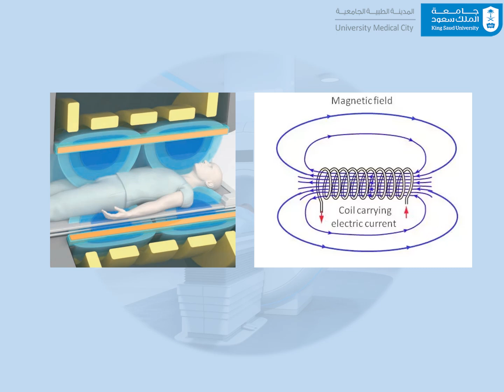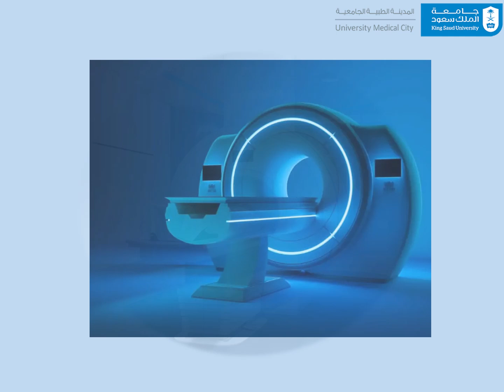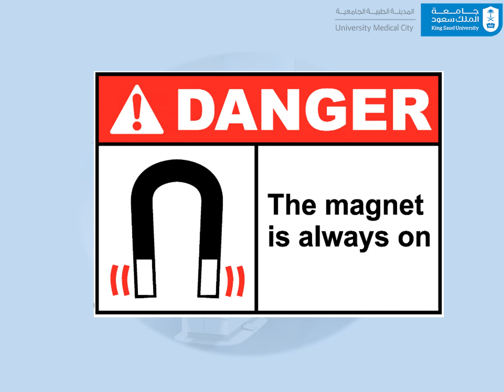Superconducting magnets are the most commonly employed magnets in clinical imaging applications, as they are capable of generating higher magnetic field strengths. The magnet for this kind of MRI scanner is always on, even if it is not being used. In the event of an emergency, these superconducting electromagnets can be quickly shut off, or quenched, at any given time.